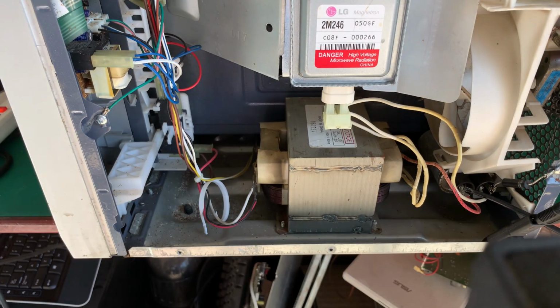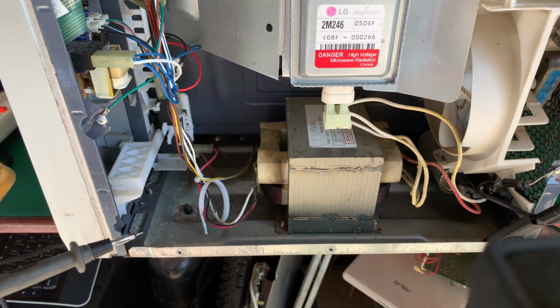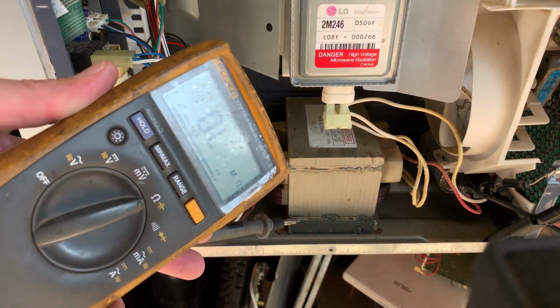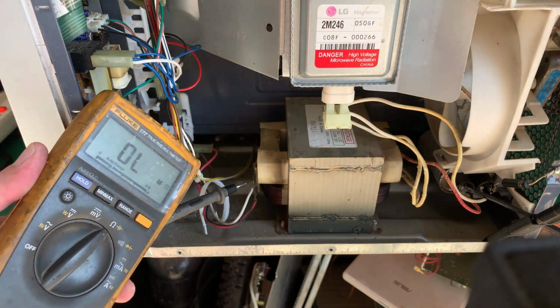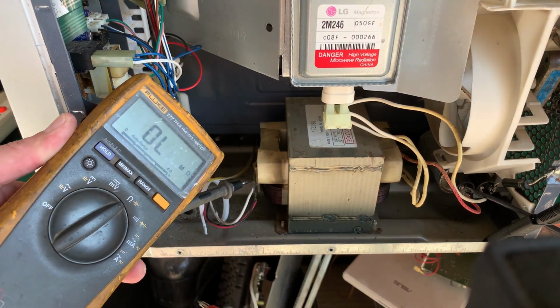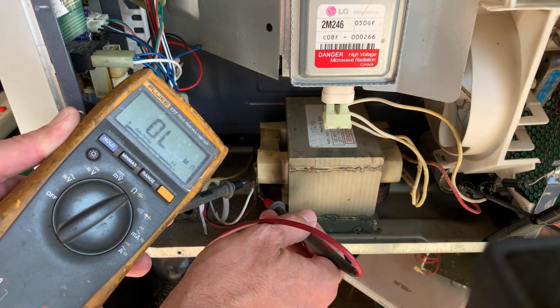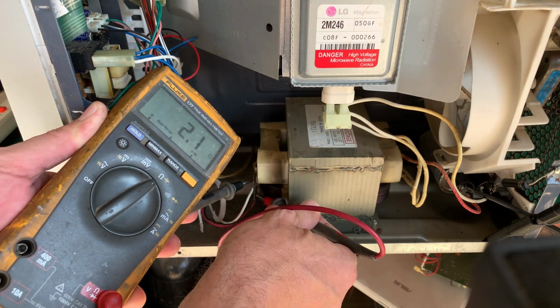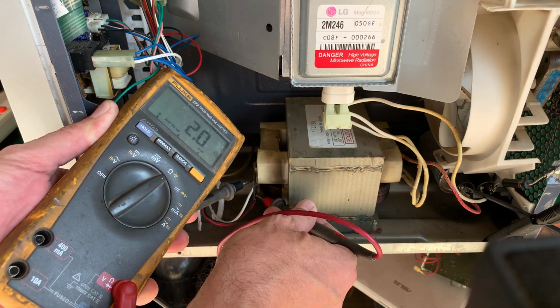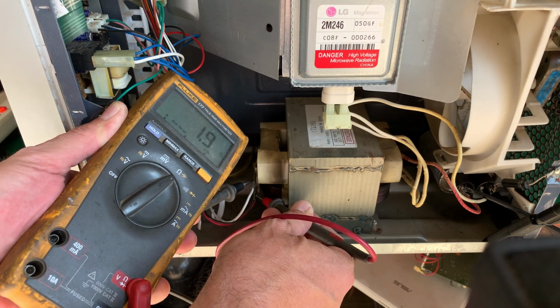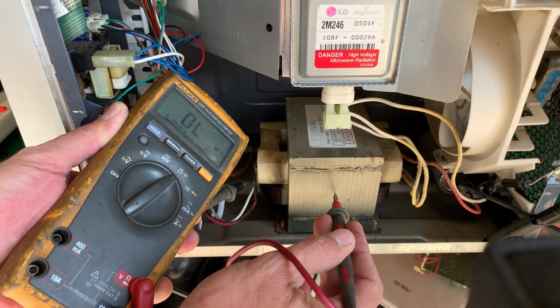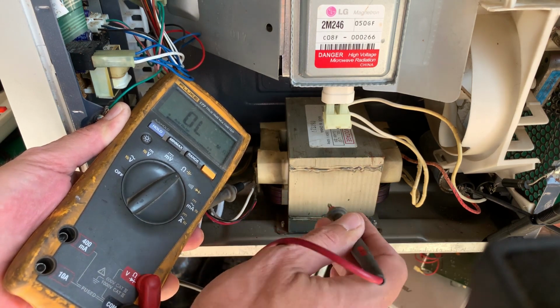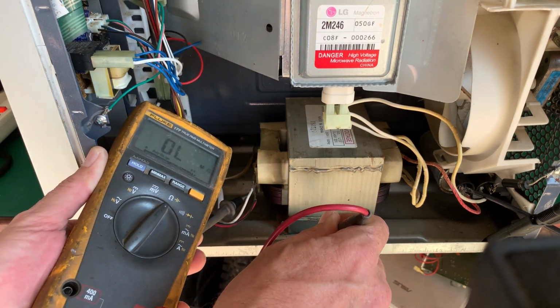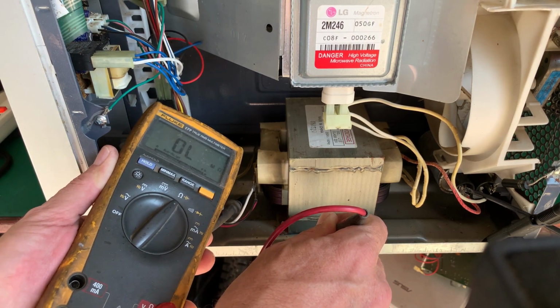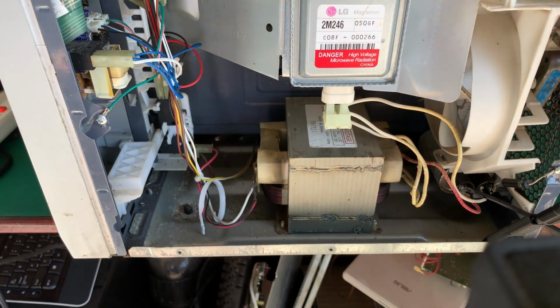Right, so here we are. The first thing I'm going to do, remember this thing is dead, I'm going to set my multimeter to resistance, to ohm scale. I'm just going to put it on the first side of the primary, and I'm going to put the next lead on the second side of the primary, and I'm going to measure the resistance of the winding. 2.1 ohms, that is fine. It should be that low. If I take either winding down, I measure to the case of the transformer or the chassis, it should be open circuit, and I'm going to do that with both sides. So that tells me the primary side of that transformer is fine.